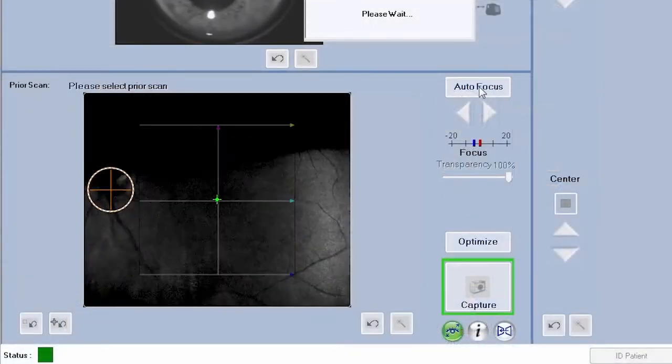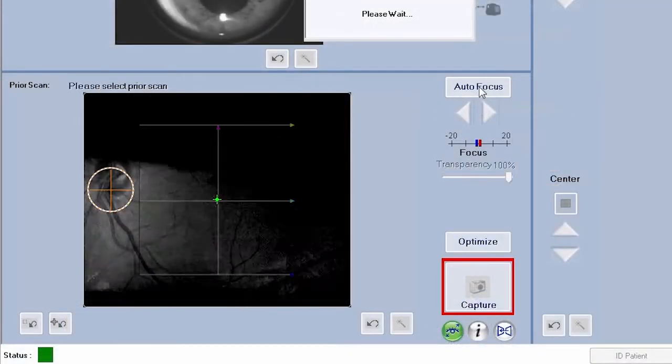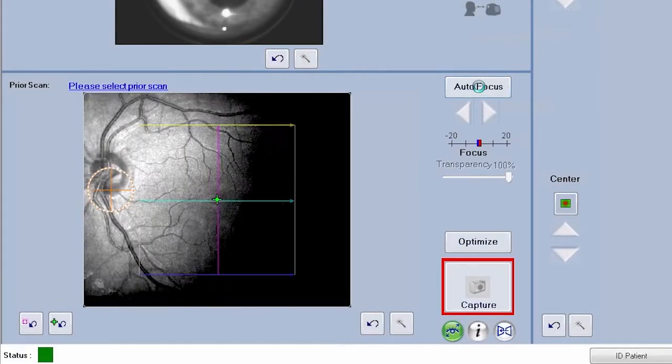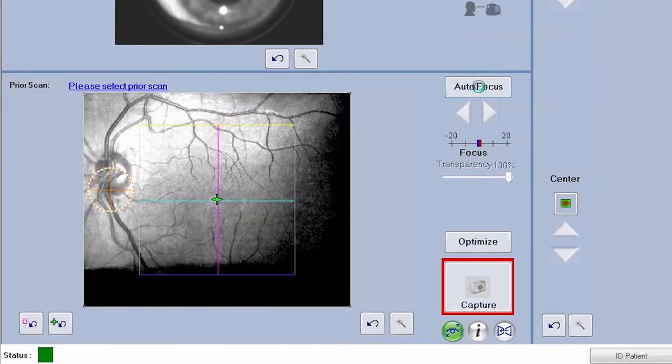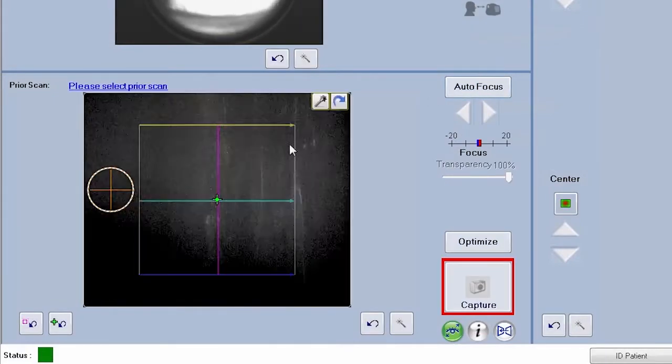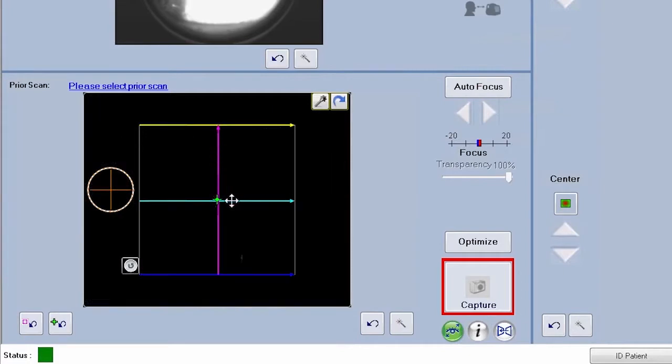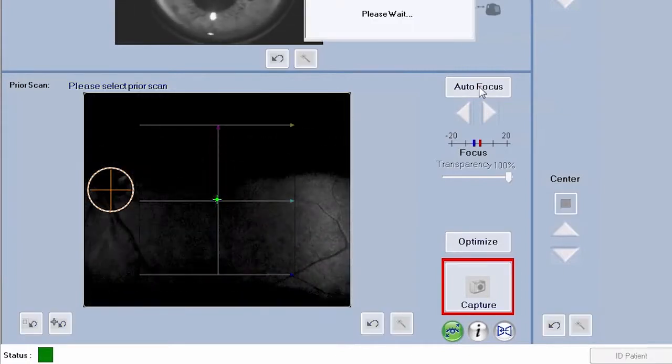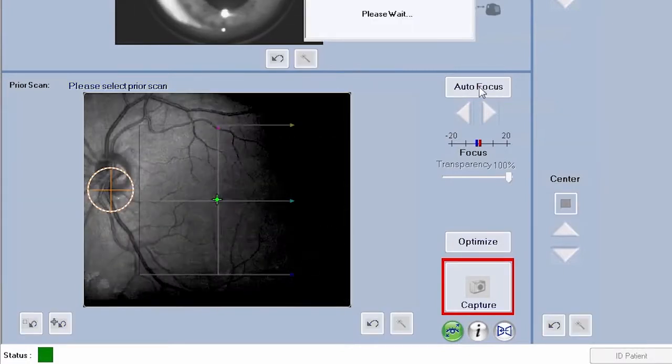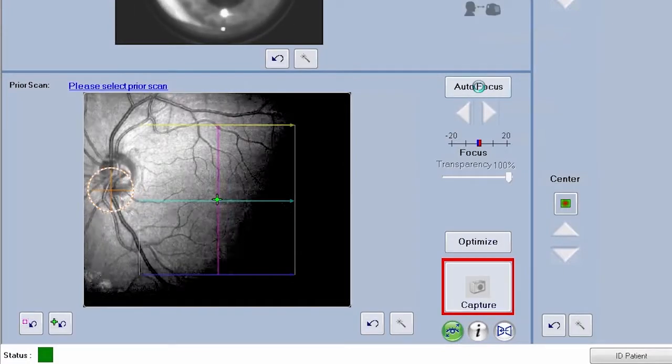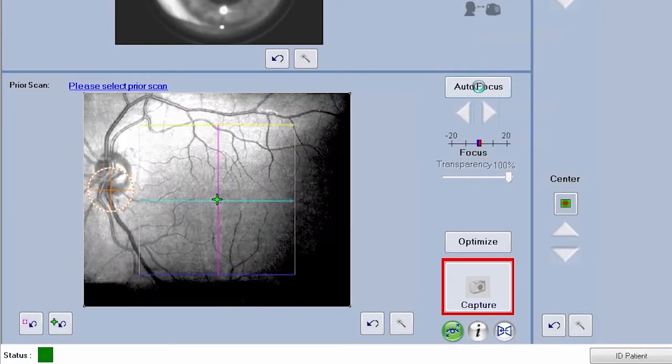After aligning the iris, focus the fundus image next. You can use the auto-focus button or adjust manually. The focus should be sharp and clear, preferably with good visibility of the branching blood vessels.